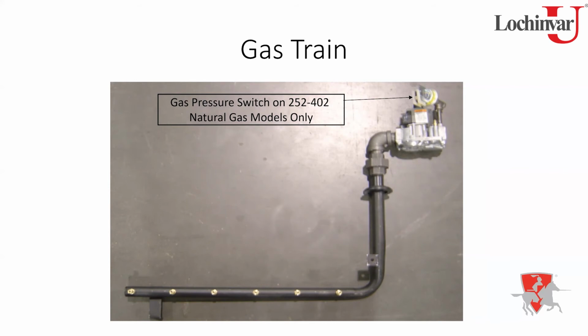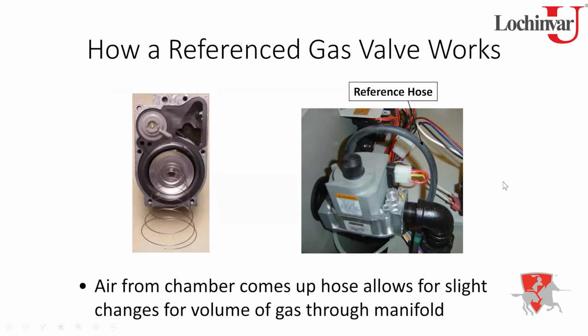Yeah, the orifices, for some reason, especially LP, spiders love LP, and they will build nests in those orifices, so they'll plug them up. So yeah, that's a good point. If it's been sitting off for the season, go through and clean those out and make sure that those are unobstructed. Now, how the valve works and how we're going to set this valve up, this is what's referred to as a reference gas valve. All that means is basically that the regulator is referencing the front chamber, right?